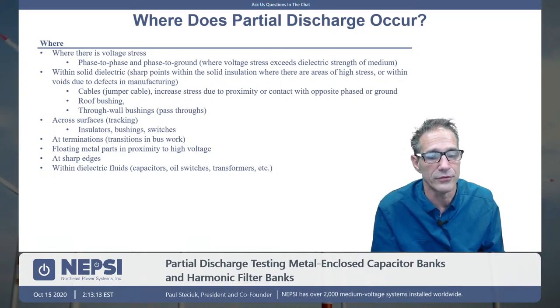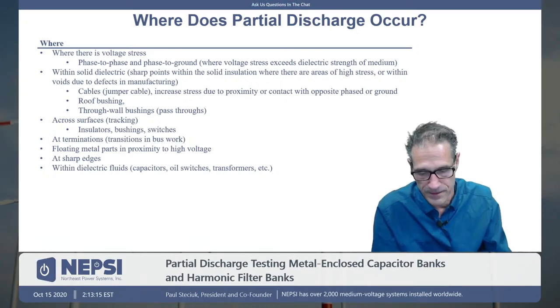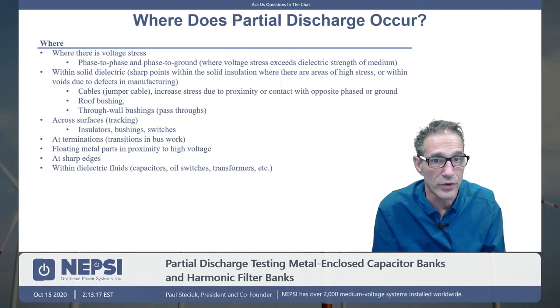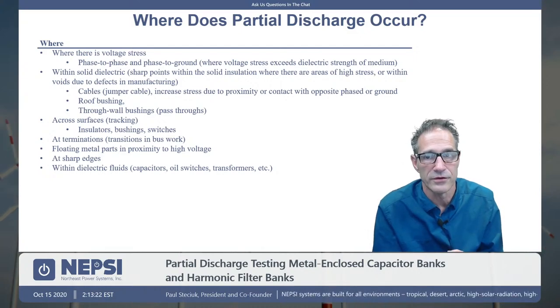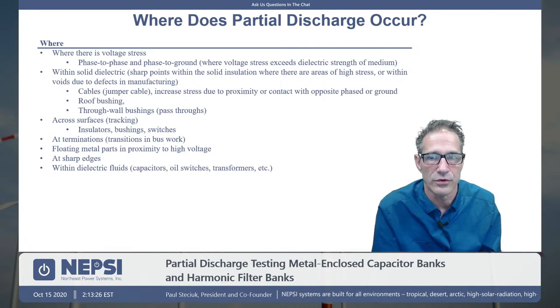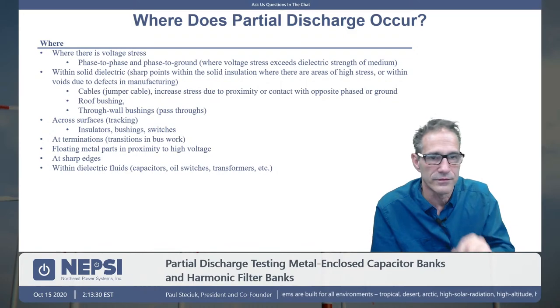A bushing that was manufactured with an internal defect might be a proper design, but it has an internal defect. So we commonly see this with the jumper cables, roof bushings, and through-wall bushings are key places where you might get partial discharge. You can also get it across the surface of an insulator.